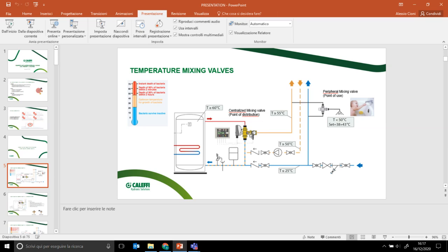Of course, in case of any failure in the probes, if the probes are giving a bad signal, or if the actuator has some issues, you will have some alarms blinking on the display and reported to the BMS system. But consider that these kind of units are very robust. So they are built and engineered to last several years. If you remind when we faced the Ritz-Carlton Hotel in Riyadh, I told you that the units are running since 2007, and they are for real. We have been contacted a couple of years ago just for a spare probe and a spare gauge, but the units were running very, very fine, even if they were quite old. So the valves are very, very, very resistant and robust.